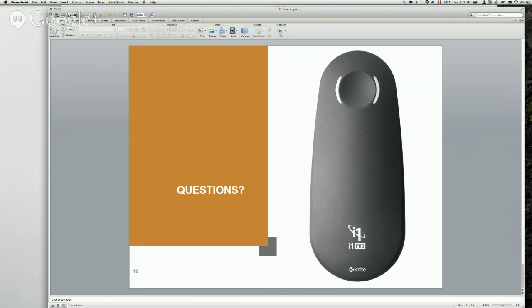Fantastic. Next question. Can the old i1 iSis be converted for M1 measurements and the other new features? Yeah, unfortunately, the answer is no. That's something we really were hoping could be done, but the reality was once we did the internal construction changes and the work to do the special calibration that M1 really requires, to do that would be essentially taking the car down to the frame and rebuilding it back up. And at that price, it would be like restoring a classic car. It would be more expensive than the car was. Right. Makes sense. Yeah, and got the full warranty and everything.